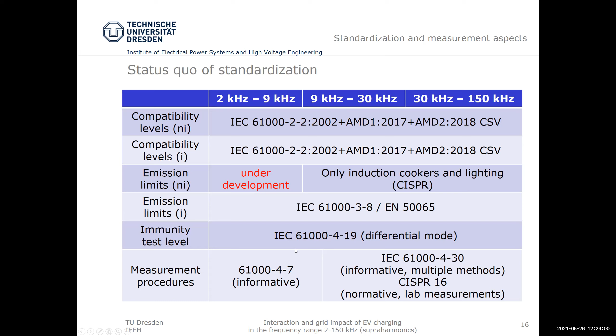I will give you a little more detail about that on this slide, showing the framework for measuring conducted non-intentional emission. As I said, there is a laboratory measurement method according to CISPR 16, but this is usually used just for measuring the equipment emission in the lab. For the compatibility levels, the utilities usually also want to measure the disturbance levels in the grid in order to compare them with those compatibility levels. Therefore, they usually use a grid measurement method, which is defined in the standard IEC 61000-4-30. But 4-30, in its current third edition, has only an informative annex suggesting 3 different methods.